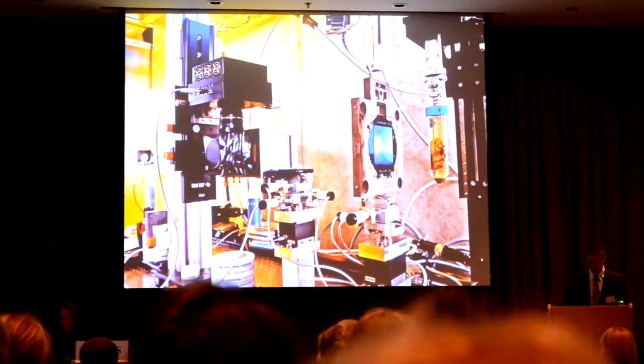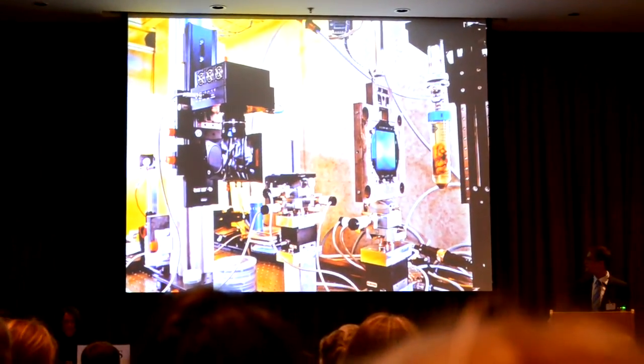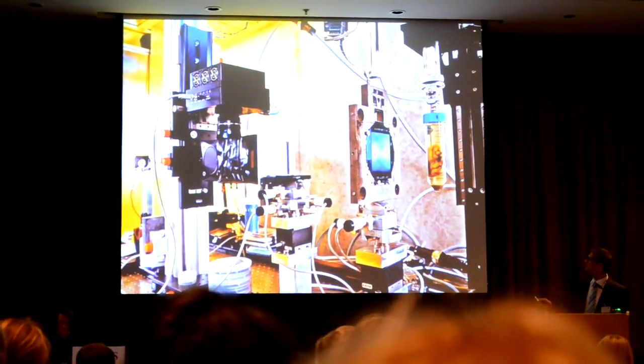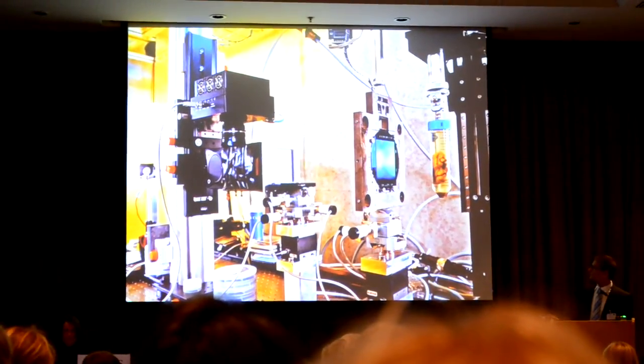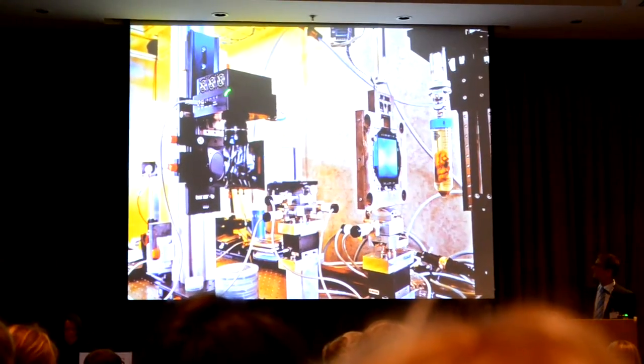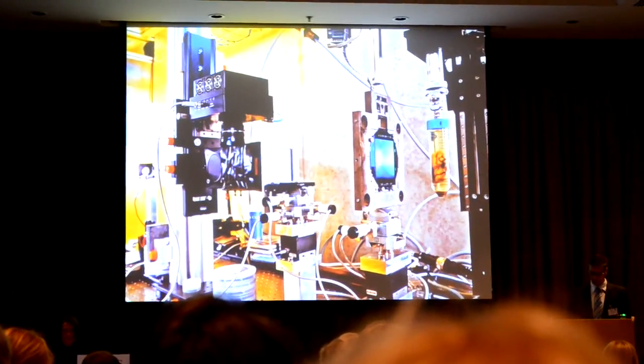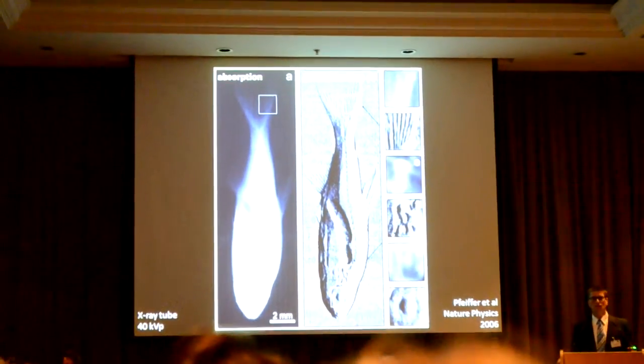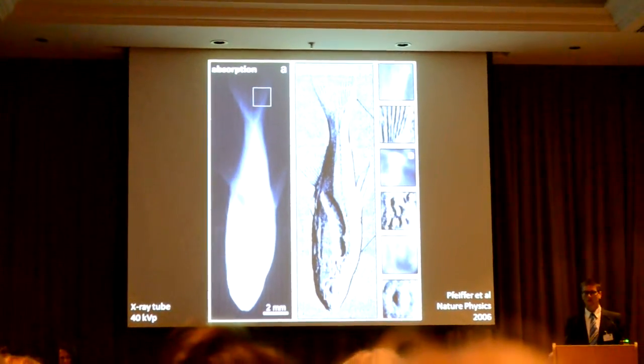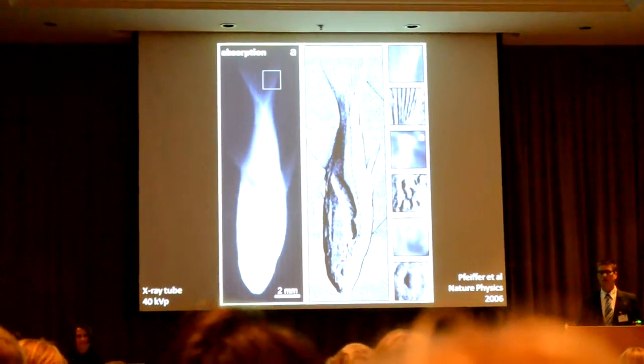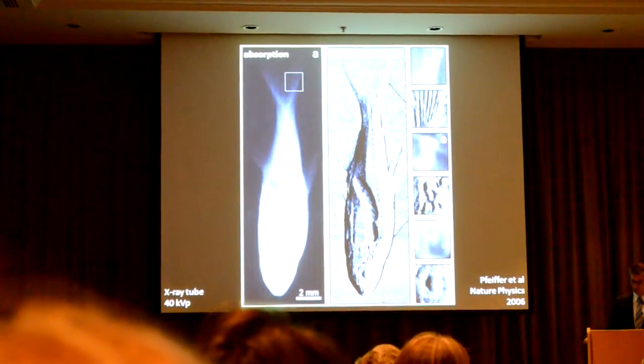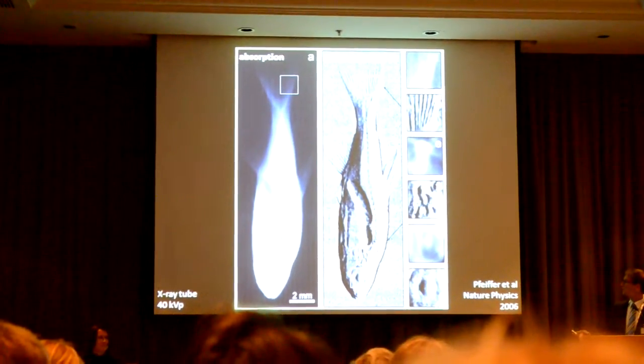We demonstrated this in 2006 for the first time using a very prototypical setup. You can see some mechanical components thrown together, a little phase grating sitting here, another phase grating sitting here, a very simple detector of just a scintillator with a mirror in the CCD, and some object in the beam. With this very crude setup we were able to show that you can actually obtain such differential X-ray phase contrast images in reasonable quality with a standard polychromatic X-ray tube source.